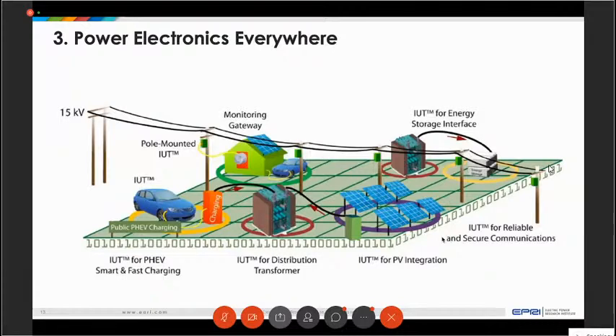Most of these power electronic devices can be operated at different power factor levels, different reactive power levels. That's one of the standards for smart inverters for PV systems: taking advantage of the reactive power management available from those inverters and making that part of the distribution system design.